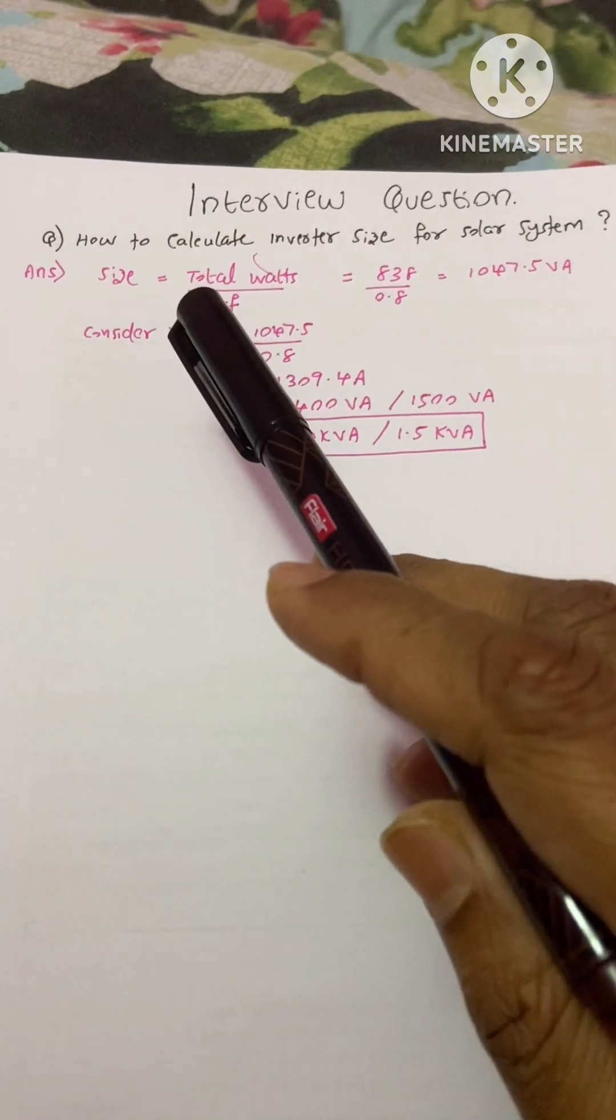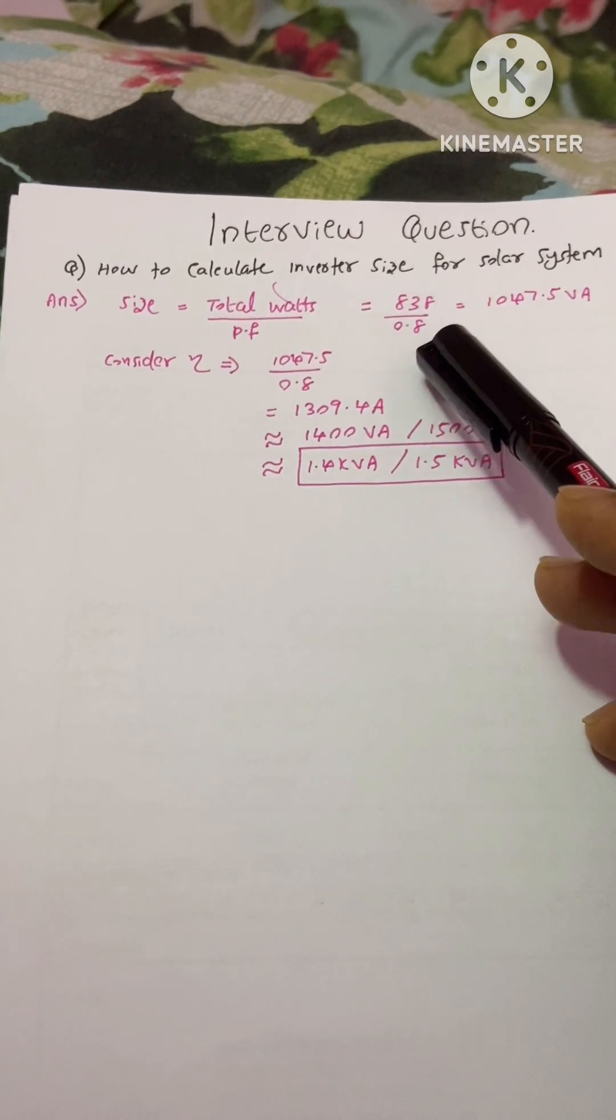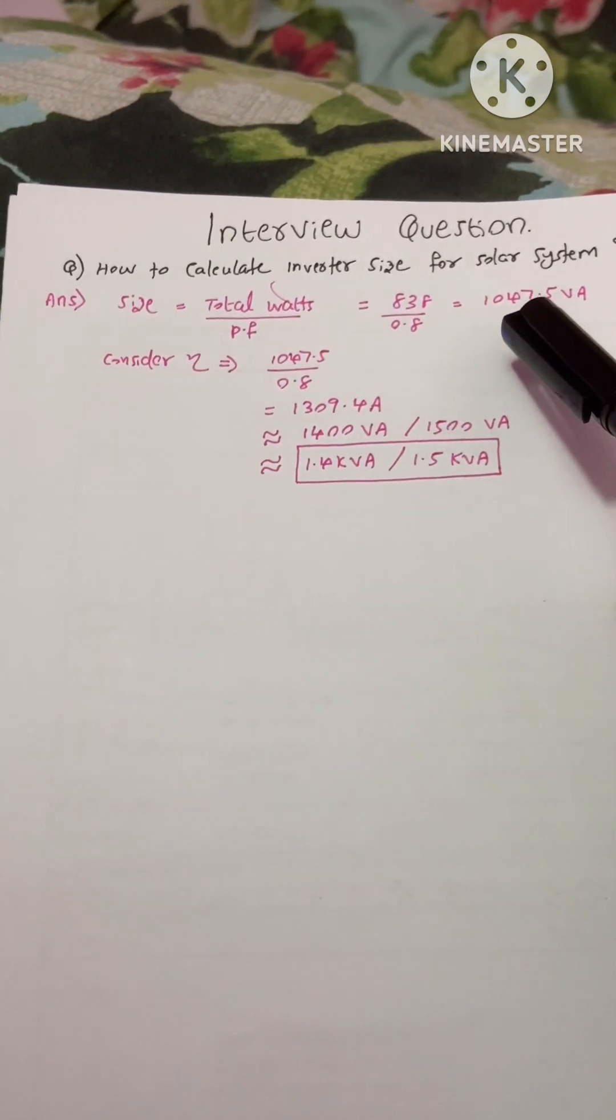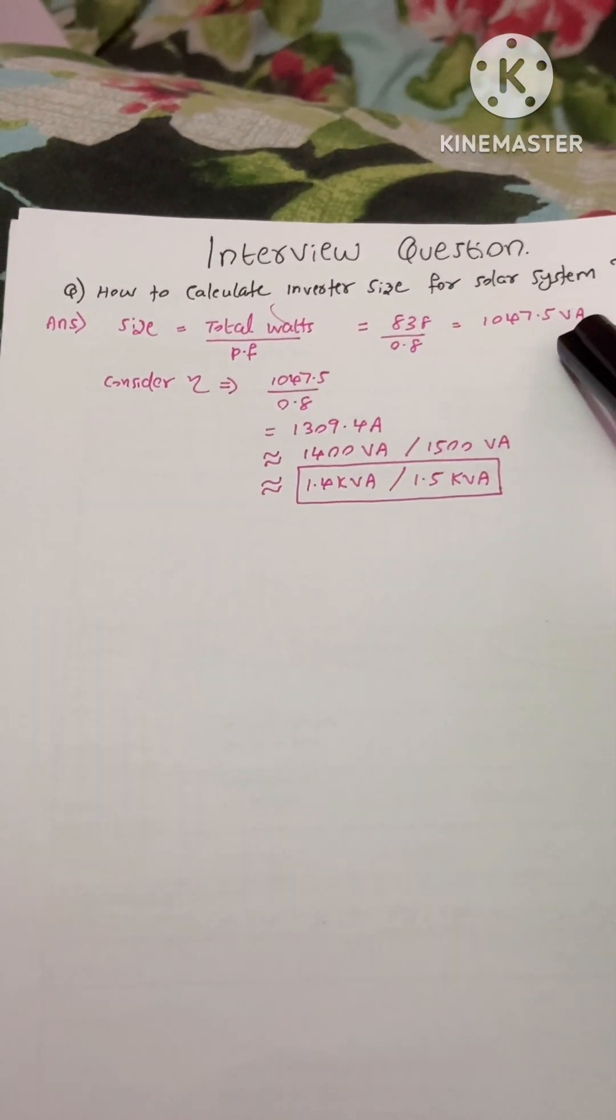Today's interview question: how to calculate inverter size for a solar system. The equation is total watts divided by power factor. Our watts is 838 divided by 0.8, which equals 1047.5 VA. First, we need to convert our watts into VA because our inverter size is always measured in VA.